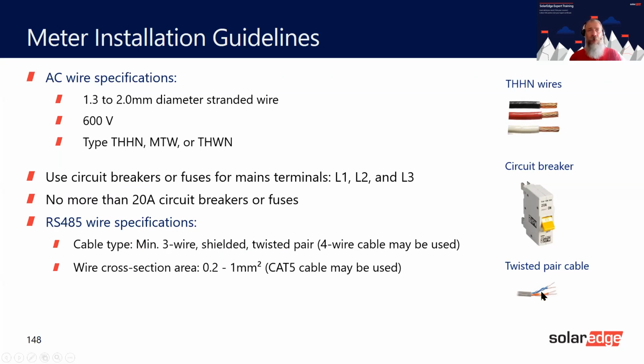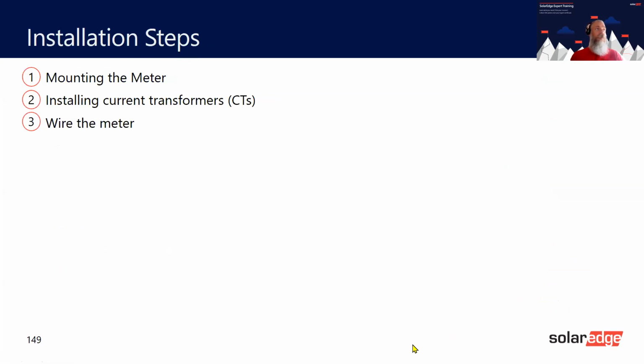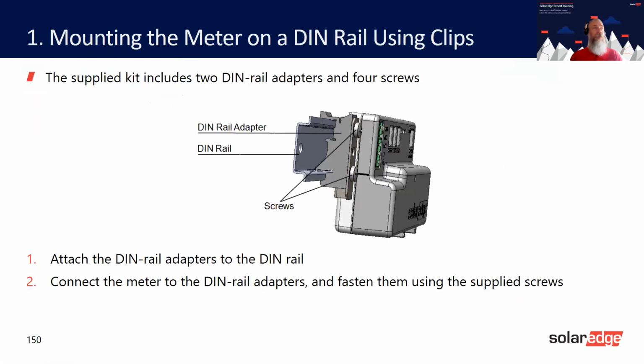You can see on here we've got the blue and the white with blue. So that would be our twisted pair, the white with blue and the blue, not the blue and orange. That's not a twisted pair. It's the blue one and the white with blue that is a twisted pair, or the orange and white with orange is a twisted pair. So mounting the meter, installing the CT. It's very important that the CT is installed in the right place and connected correctly, as well as pushed together. It must click into place, and then wiring the meter. So this is what we're going to look at.